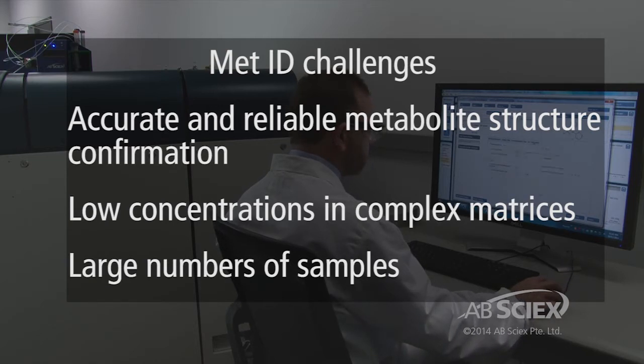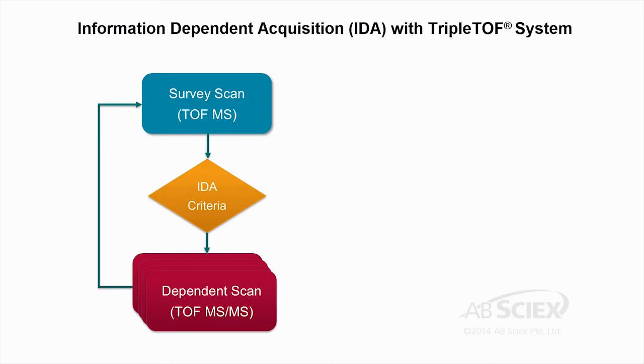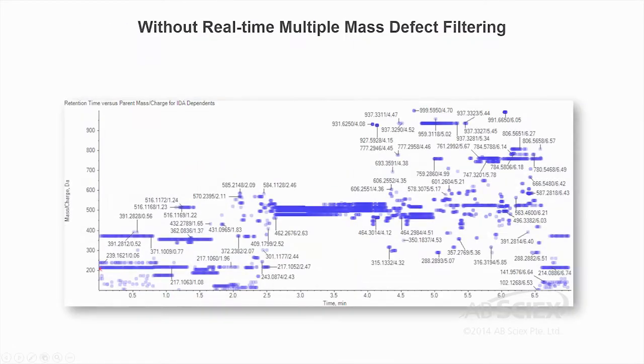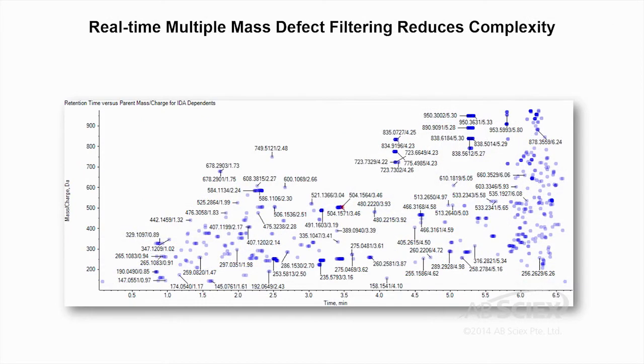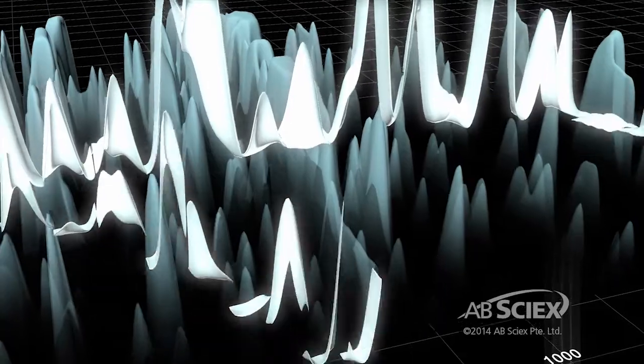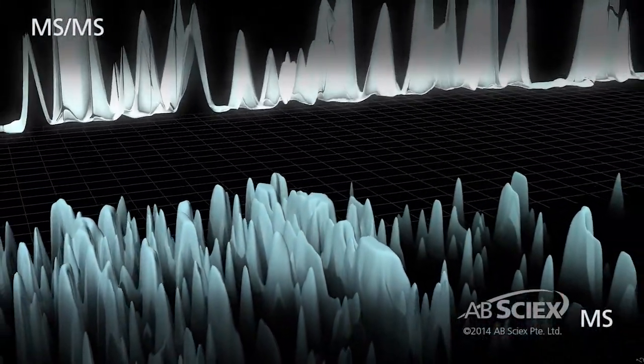Time of flight analysis provides the necessary level of mass accuracy for definitive molecular formula assignment. Structural confirmation is facilitated with the triple TOF using high resolution product ion spectra acquired either through information dependent acquisition or through SWATH acquisition. Information dependent acquisition with the triple TOF can employ real-time filters such as multiple mass defect and isotope pattern. This unique functionality can dramatically improve your ability to identify low-level metabolites in complex matrices. Alternatively, SWATH acquisition fragments all compounds creating a complete spectral archive of the sample.